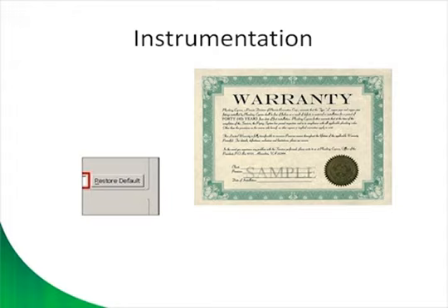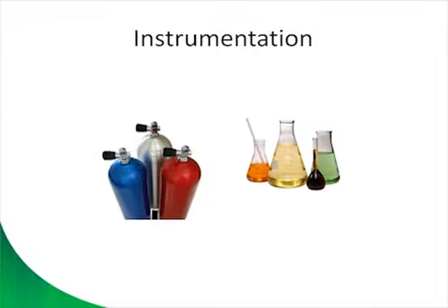What about consumables? Do you have a way to pay for consumables in the future or recalibrations? One of the things that LI-COR does with our packages is that, especially for the smaller institutions, we want to make sure that they are going to have everything they need for years and years of use. So everything's purchased upfront in the cost of the instrument, so they don't have to worry about coming up with additional costs 2 years or 3 years down the road for recalibration or something like that. So it's really important to have that maintenance plan in place for how you're going to maintain this instrument.